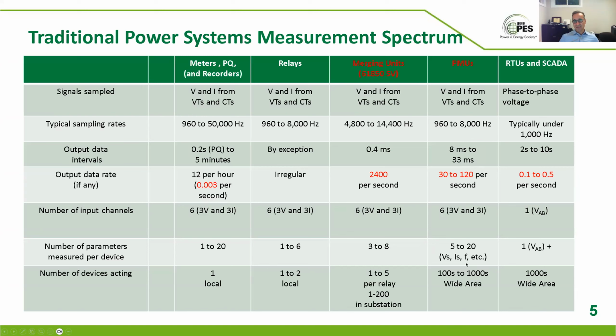Again, you could get it from many points. There are not as many PMUs around as there are RTUs per se, and they would have about 2 orders of magnitude more volume of data because they sample about 100 times more and they send more data, up to 20 parameters, not typically 1. And then as we get closer to the substation, the sampling rates and communication rates go up.